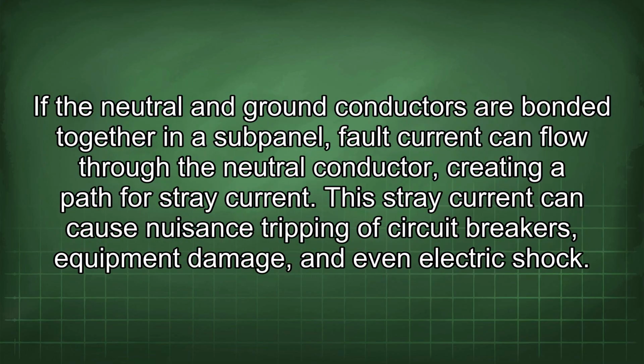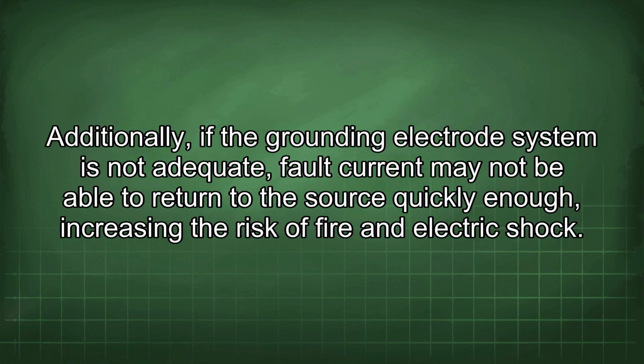If the neutral and ground conductors are bonded together in a subpanel, fault current can flow through the neutral conductor, creating a path for stray current. This stray current can cause nuisance tripping of circuit breakers, equipment damage, and even electric shock. Additionally, if the grounding electrode system is not adequate, fault current may not be able to return to the source quickly enough, increasing the risk of fire and electric shock.